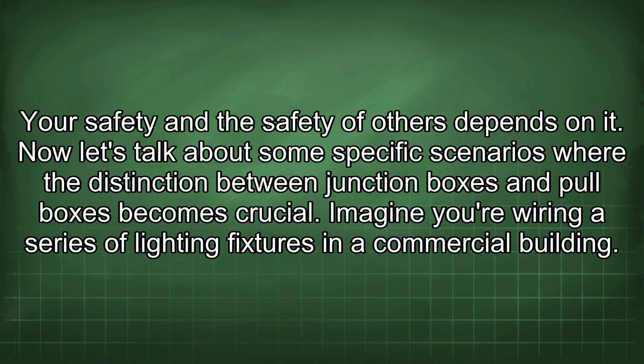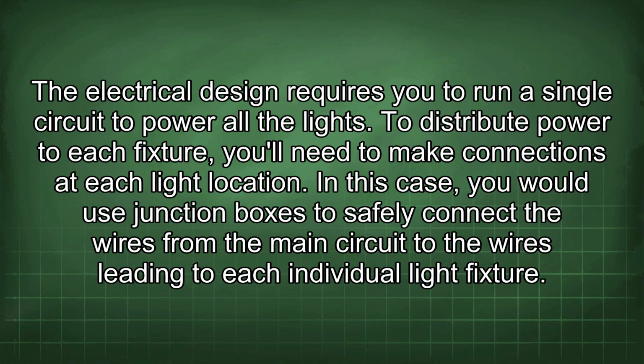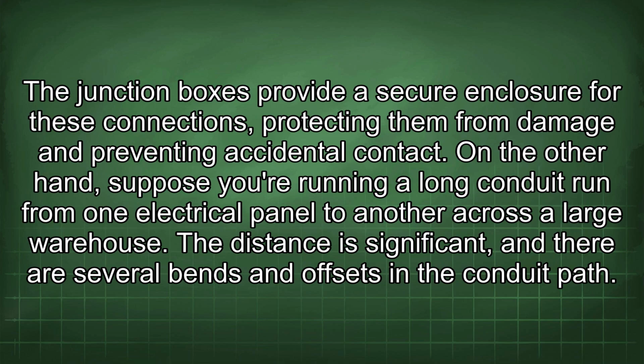Now let's talk about some specific scenarios where the distinction between junction boxes and pull boxes becomes crucial. Imagine you're wiring a series of lighting fixtures in a commercial building. The electrical design requires you to run a single circuit to power all the lights. To distribute power to each fixture, you'll need to make connections at each light location. In this case, you would use junction boxes to safely connect the wires from the main circuit to the wires leading to each individual light fixture. The junction boxes provide a secure enclosure for these connections, protecting them from damage and preventing accidental contact.